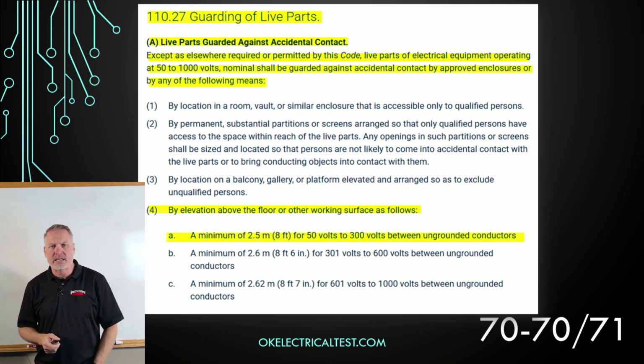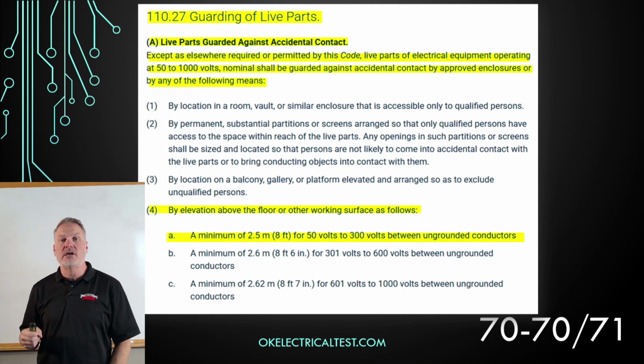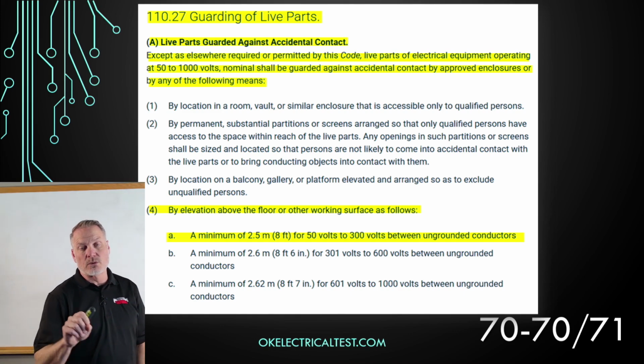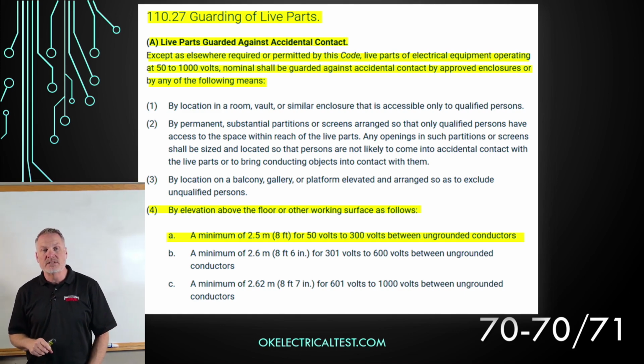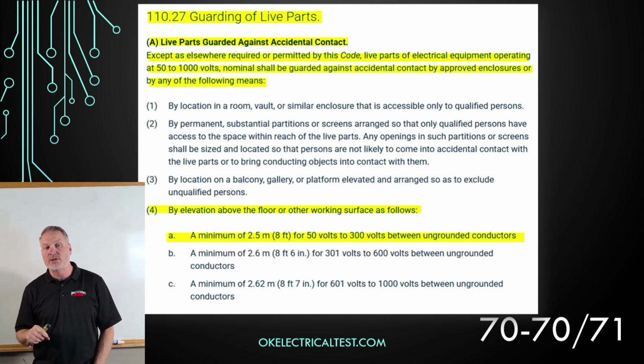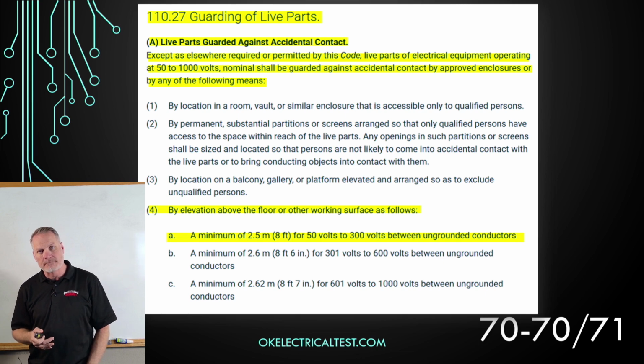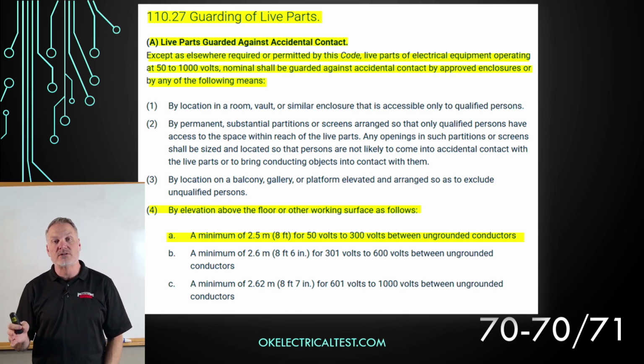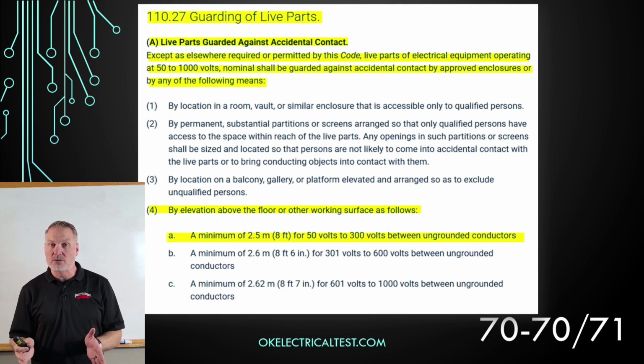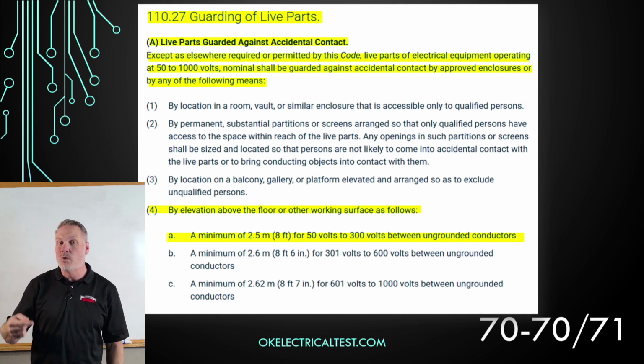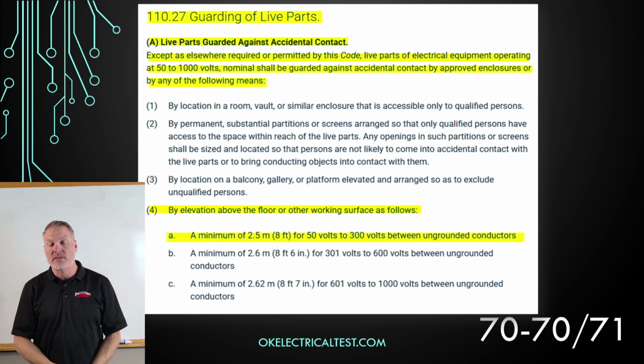Let's go to 110.27, guarding of live parts. And again, these live parts are going to be 1,000 volts or less. And so when we take a look at letter A, it says, except as elsewhere permitted or required by this code, live parts of electrical equipment operating at 50 to 1,000 volts nominal shall be guarded against accidental contact by approved enclosures or by any of the following means. Okay, so again, what do we need to do over 1,000 volts? That's addressed in another part. That's going to be in part 3. Okay, so again, part 2 only addresses 1,000 volts and less. So it says 50 to 1,000 volts. So one of the questions we start seeing on the exams is, at what voltage do we need to start guarding? And that's going to be at 50 volts.